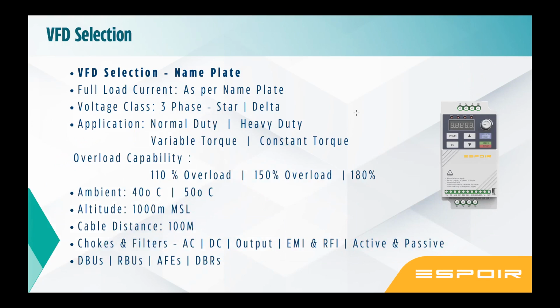Now, how should you select? There are various brands and various models available. How do you select a VFD for a particular application? Number one aspect, we need to understand the nameplate. We need to go by the motor nameplate. Anyone who asks, I need a VFD, please ask for the motor nameplate. We need to match the full load current of the motor, minimum. Then the voltage class, whether it is three-phase, whether it is a star or a delta connection.